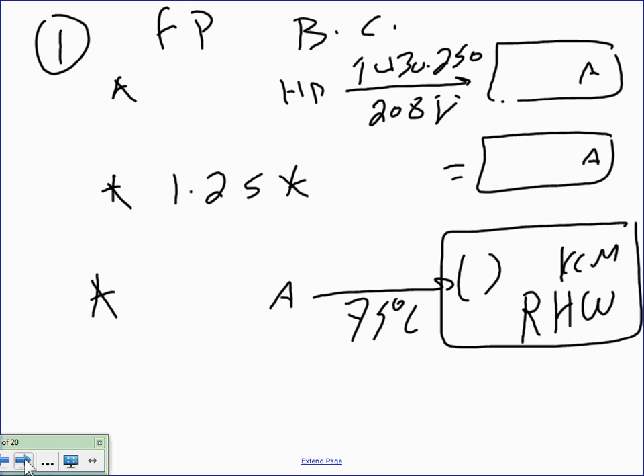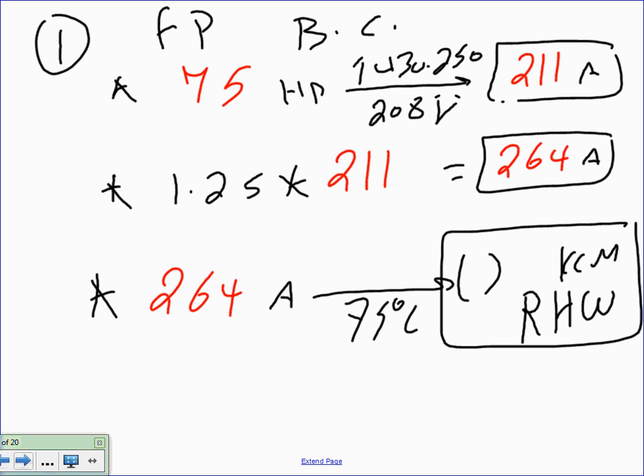Okay, let's go ahead and find the following for the fire pump. The first thing, guys, repeating ourselves over and over: the fire pump is 75 horsepower. By now you need 430.250. Now we're going to go to 208, because the equipment is rated for 208. That gives you 211 amps, right? The second thing you need to do is multiply by 1.25 because it's a continuous load. What do you get? You get 264 amps.